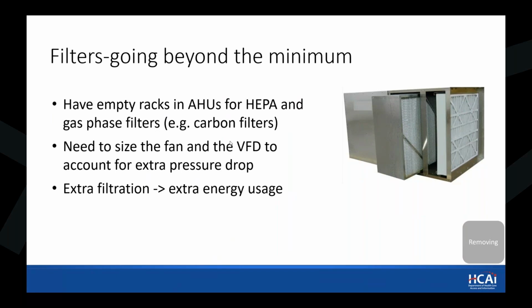Even gas phase filter, as we said, at this time Guideline 44 is leaving the gas portion as optional, but the committee is still meeting and we're looking into adding more requirements about the VOCs and the gas phase filter, carbon filter, or even going into the reactive cleaning. When you do that, obviously you have to make sure that your HVAC system, for example your fans and your VFDs, are designed to handle the extra pressure drop if you want to add more filtration. And of course, keep in mind that extra filtration will always come with extra energy usage.